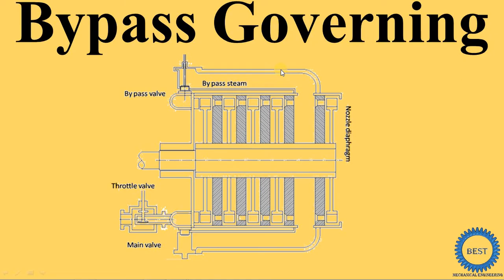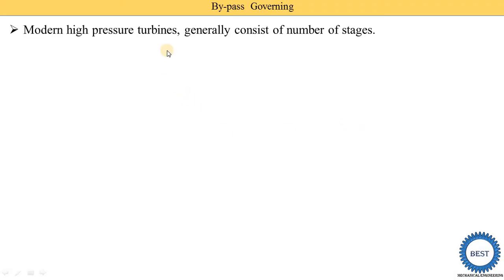In a bypass governing system, there is no blockage or maintenance going on, but its name is 'bypass governing' because additional quantity of steam is required in the further stages. We already know that the turbine consists of a number of stages. After the first few stages, additional steam is required due to loads greater than the economical load. This bypass steam is added and mixed with the steam coming out from the high pressure stage, and then supplied to the further low pressure stages.